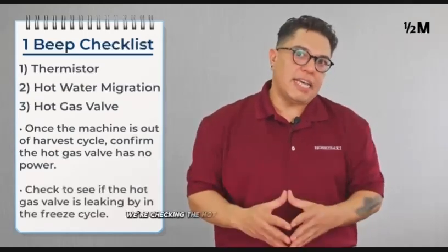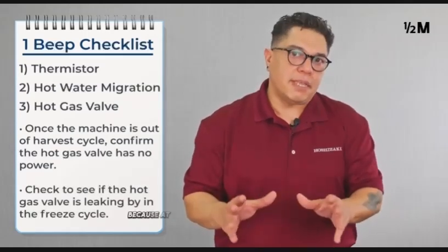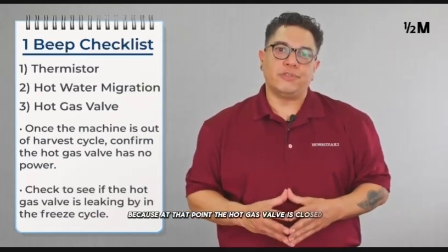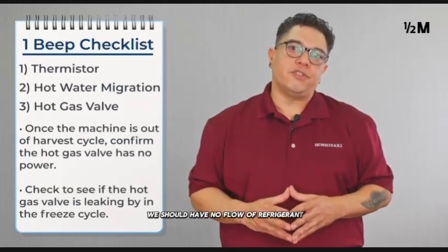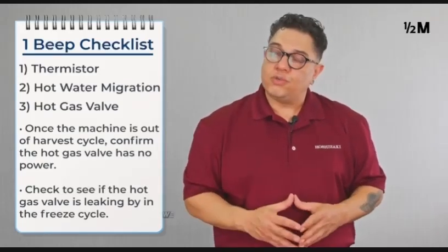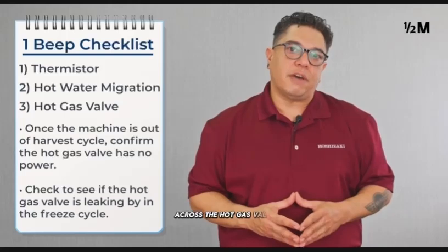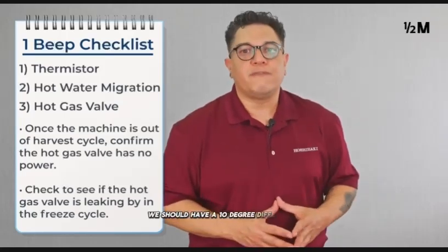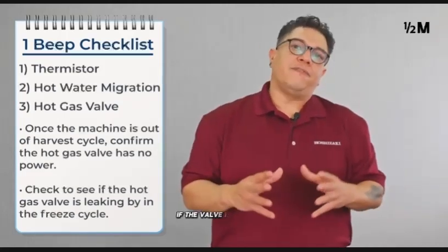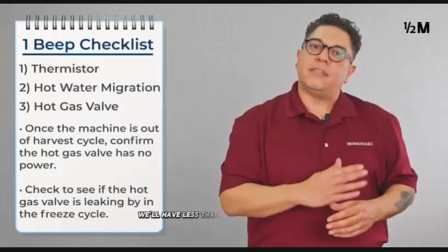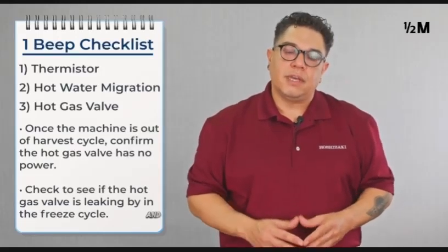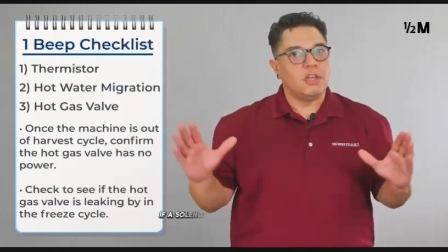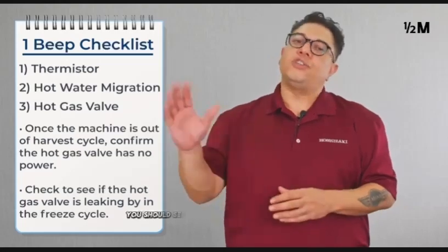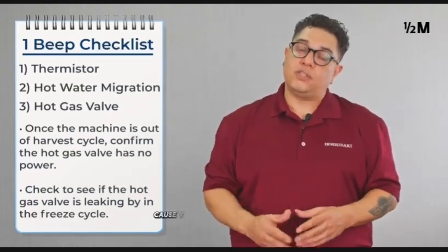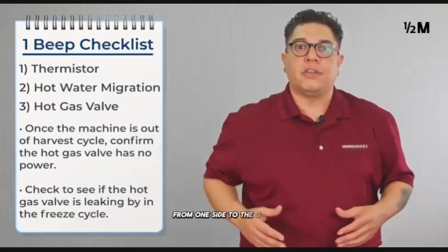Now, we're checking the hot gas valve in the freeze cycle because at that point, the hot gas valve is closed. We should have no flow of refrigerant at that point. What we're going to do is take a temperature across the hot gas valve. We should have a 10-degree differential. If the valve is leaking by, we'll have less than a 10-degree differential. And I want you guys to understand that if a solenoid valve was energized, you should see the same temperature on both sides because you have refrigerant flowing from one side to the other.